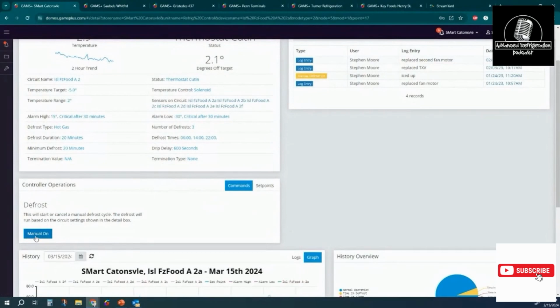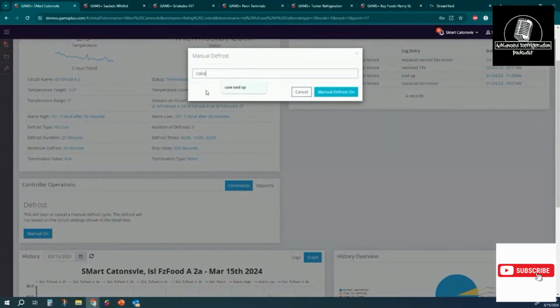So we can throw this one in defrost. I can see it's hot gas, I can see that it has a minimum defrost, and its standard defrost is 20 minutes. So I put it in that manual defrost.